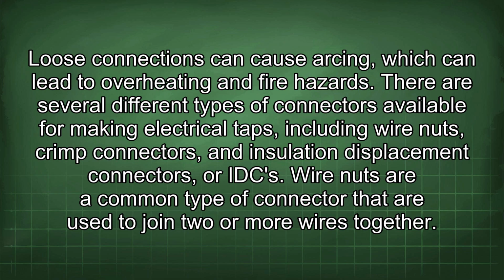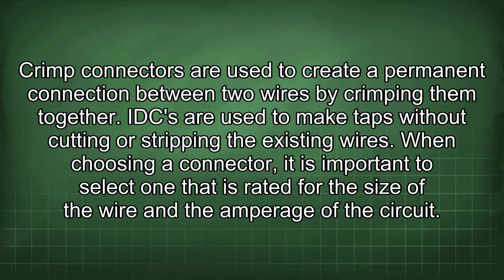There are several different types of connectors available for making electrical taps, including wire nuts, crimp connectors, and insulation displacement connectors, or IDCs. Wire nuts are a common type of connector that are used to join two or more wires together. Crimp connectors are used to create a permanent connection between two wires by crimping them together. IDCs are used to make taps without cutting or stripping the existing wires.